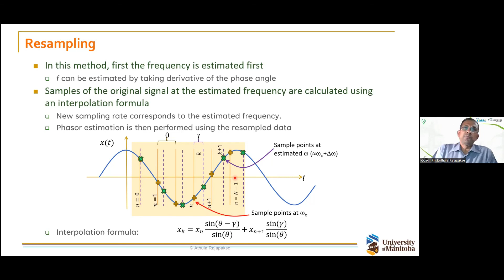This is normally called the variable sampling rate method. It's often used in protection relays, but typically not used when doing synchrophasor-based estimation. One problem is that when you're using time tags, you need to report a certain number of cases per second, and the time tags should be fixed values. So we don't normally use this resampling or variable sampling rate method when computing synchrophasors.